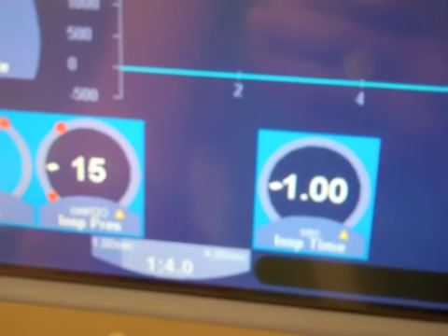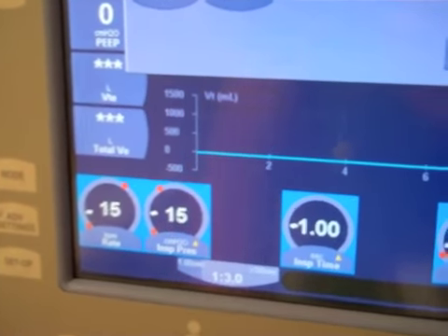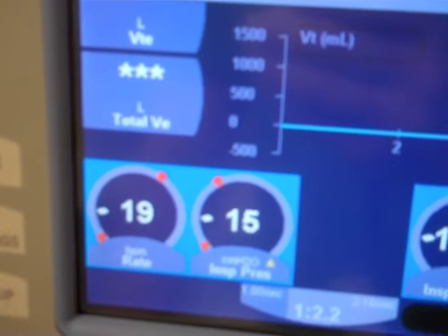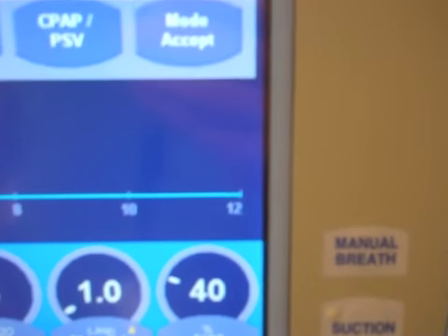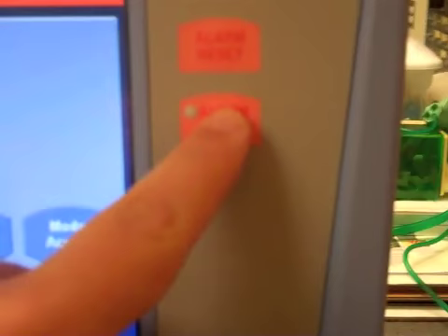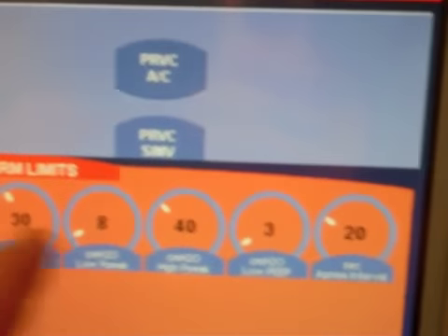Let's say I wanted to set a respiratory rate of 15. I would touch 15. It's going to highlight blue. Turn my rotary wheel until I actually get the desired setting I want, and then touch it again to confirm it. It's very important. So remember, touch, turn, touch on the Avea. Make sure you go through and set all of your parameters to what you want, and go into your alarms to set your alarms to what you want your alarm scenarios to be. Once you're happy with all of that, you can go ahead and hit mode accept, and you'll start ventilating.